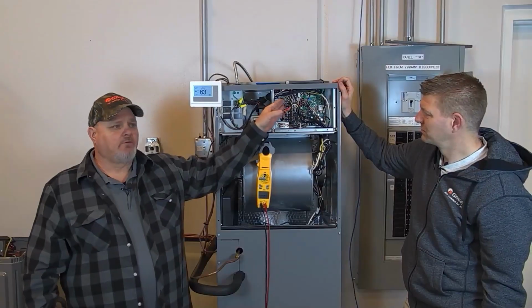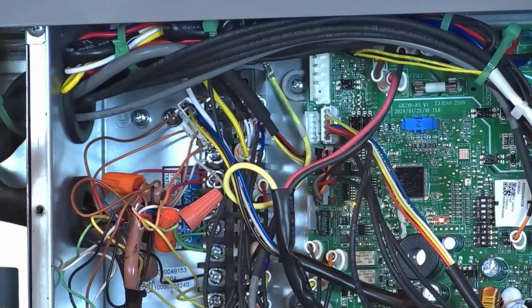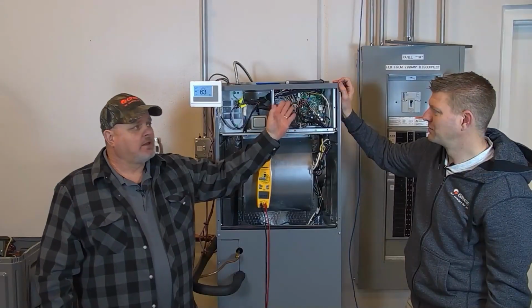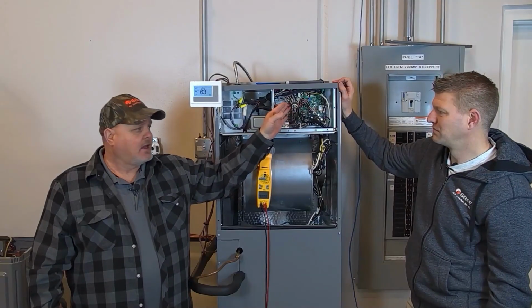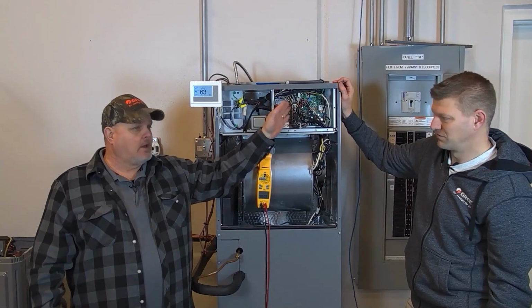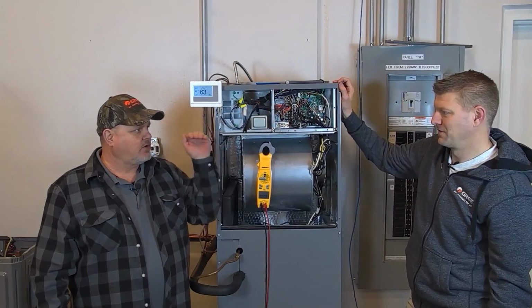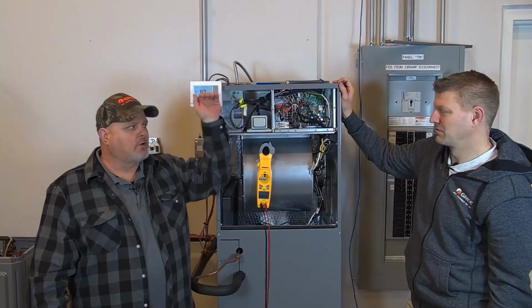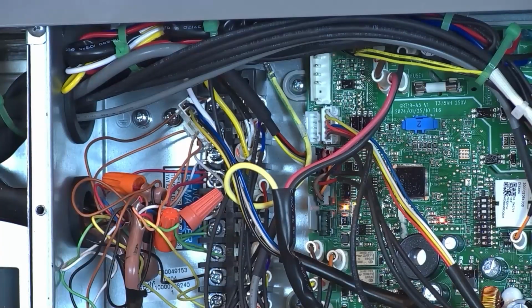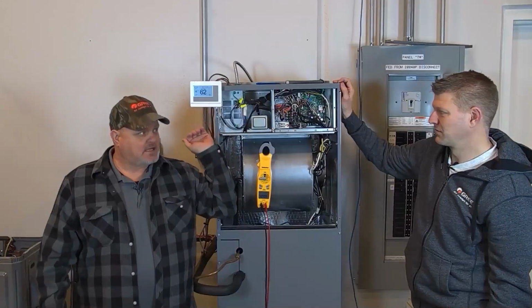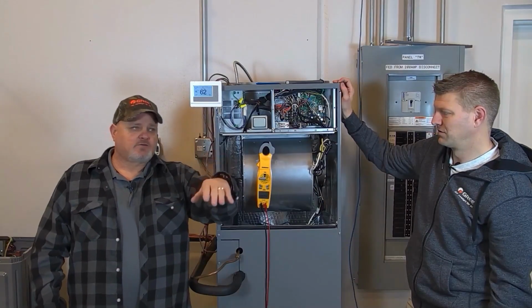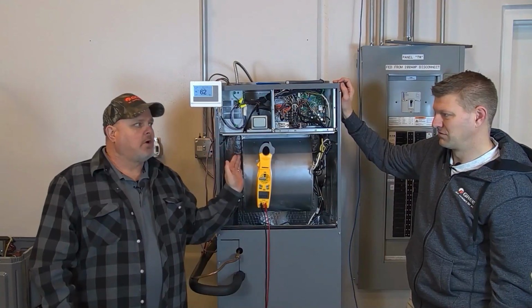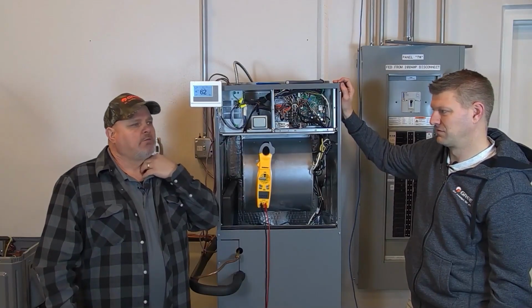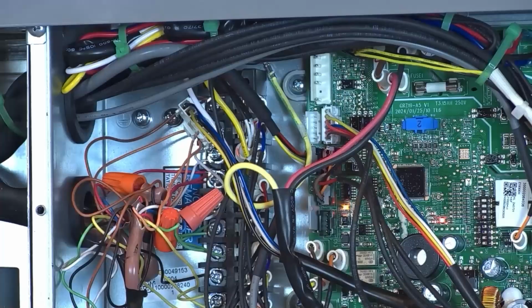But as you can see from the voltage readings we did, the board is doing exactly what it's supposed to be doing. We got our steady 15 volts, which on the plug would be the black and white wire on those pins. And then we went black to where the yellow wire would be on that pin, and we're getting that steady increase of DC voltage. So it's wanting to start the motor, and it's going to stop because we're not getting any feedback voltage on that blue wire. That's what it's looking for. It sends the PWM signal out, and it looks for that feedback voltage back so it knows the motor actually came on and is running. So if the motor's unplugged or the motor's bad, you're never going to get that feedback voltage.